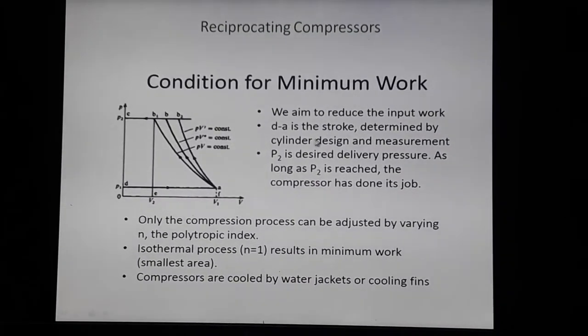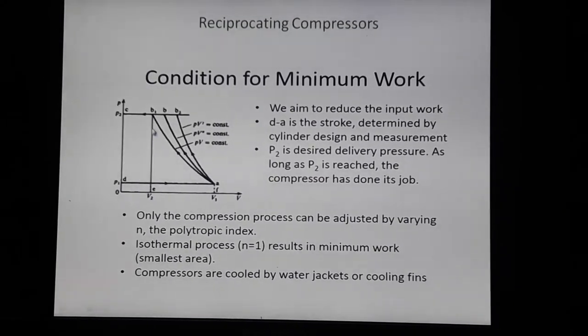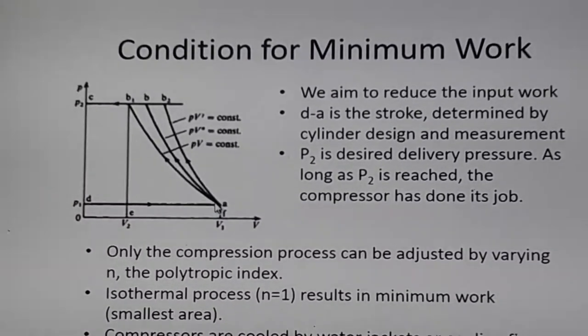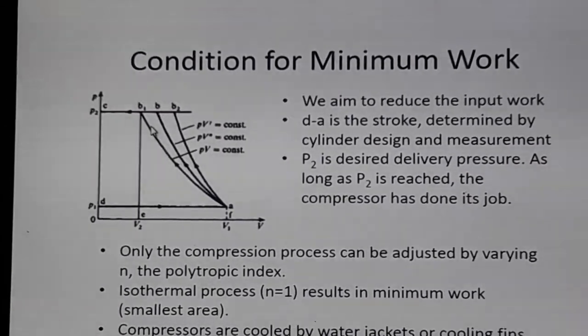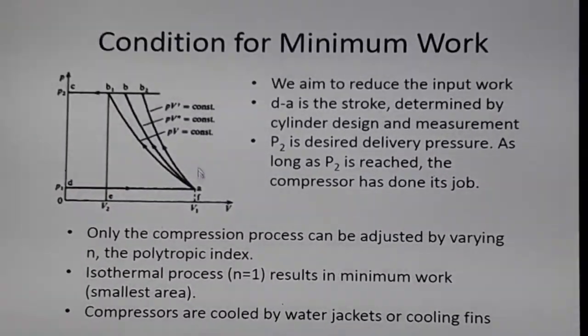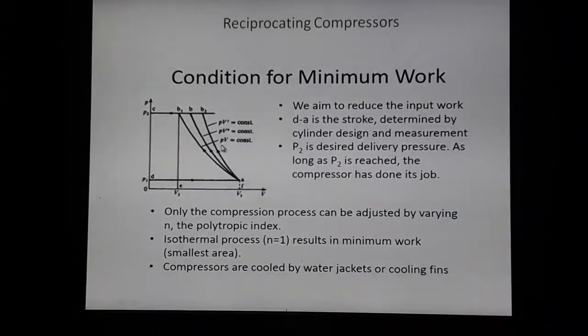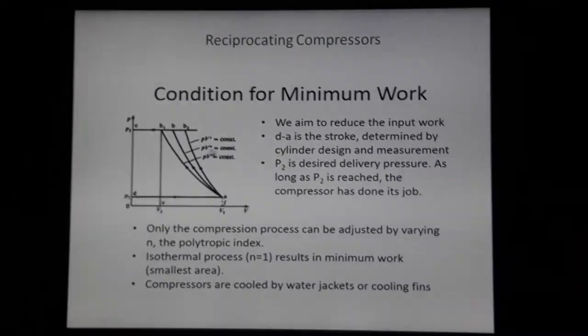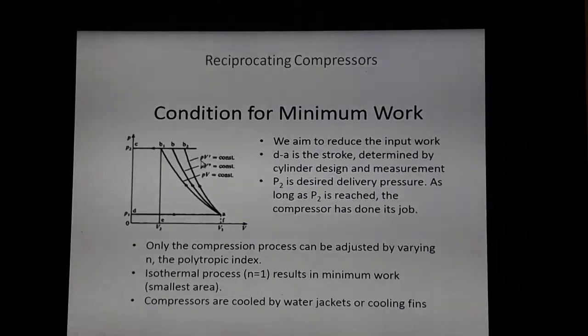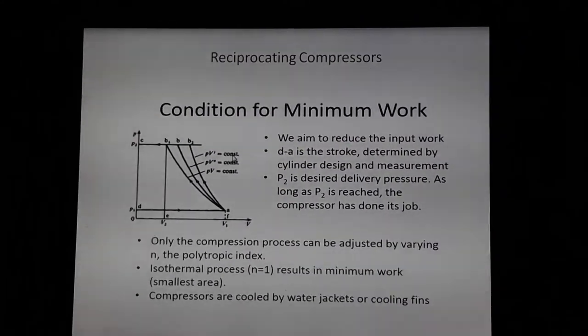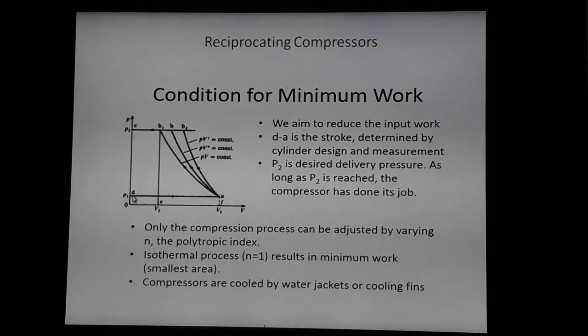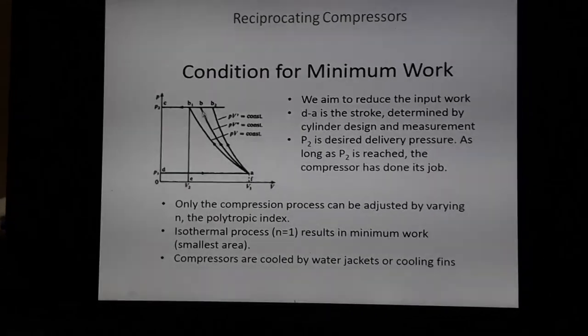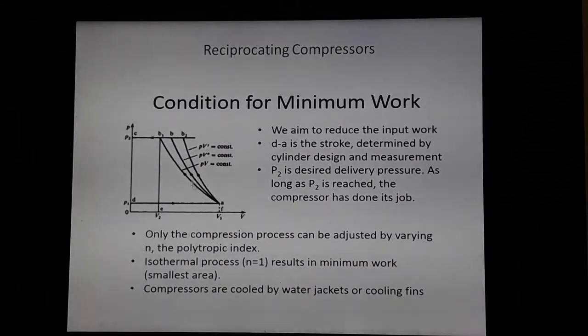In a compressor, compression may be adiabatic, polytropic, or isothermal. In the PV diagram, A to B1 is isothermal compression (PV = constant), A to B is polytropic compression, and A to B2 is adiabatic compression (PV^γ = constant). The work for the isothermal process is area A-B1-C-D, for polytropic it is A-B-C-D, and for adiabatic it is A-B2-C-D.